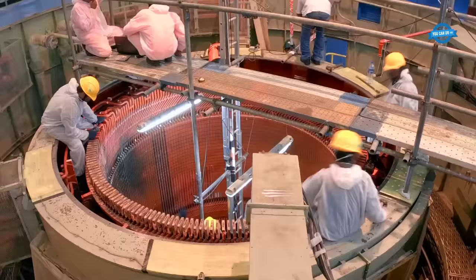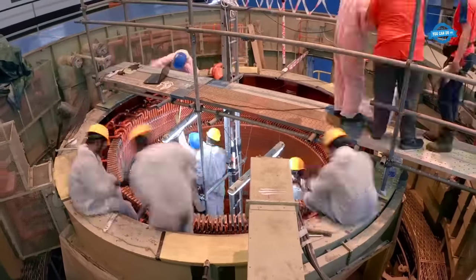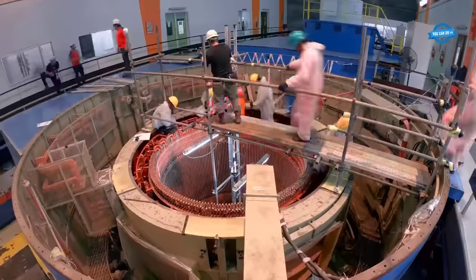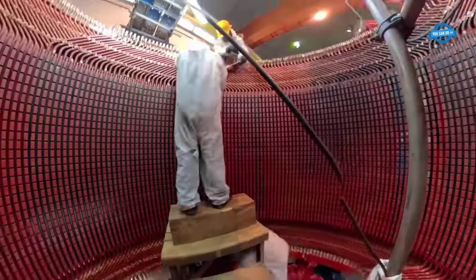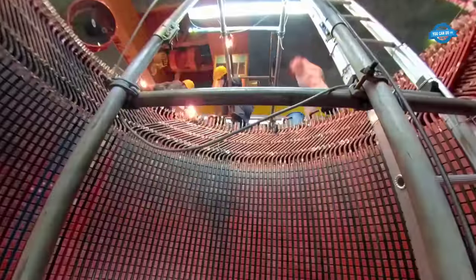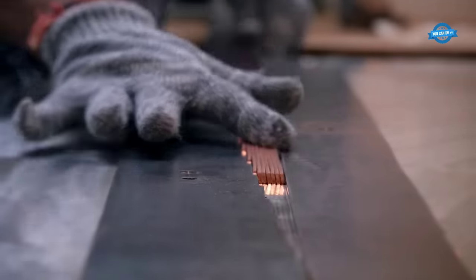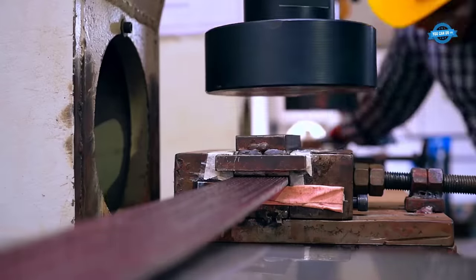The process began in August when smoke was detected from Unit 2 of the generator. It was discovered that the stator had been burnt and the core was damaged, necessitating immediate repairs to mitigate revenue losses. A technical team was assembled to analyze the root cause of the failure and develop a comprehensive solution for the rewind.